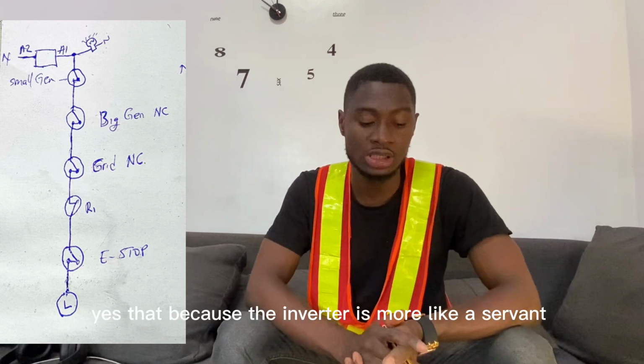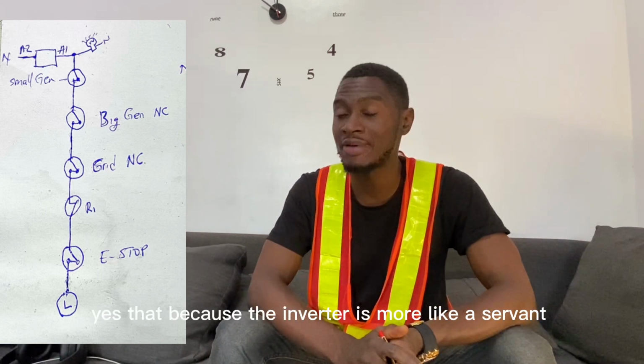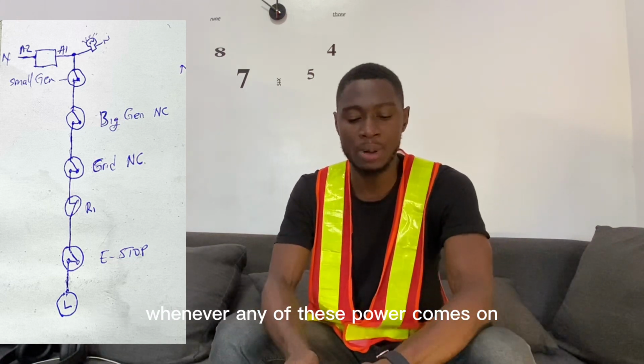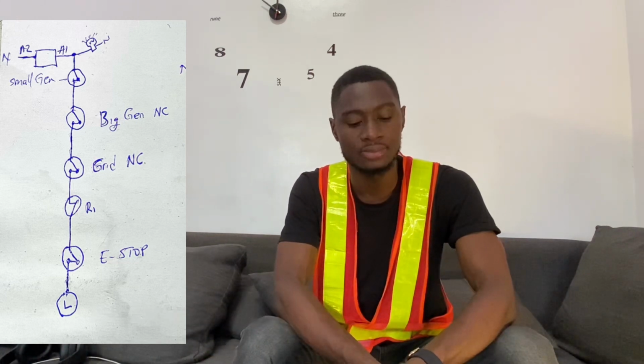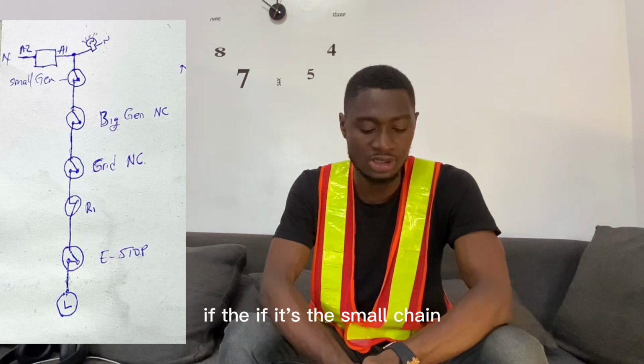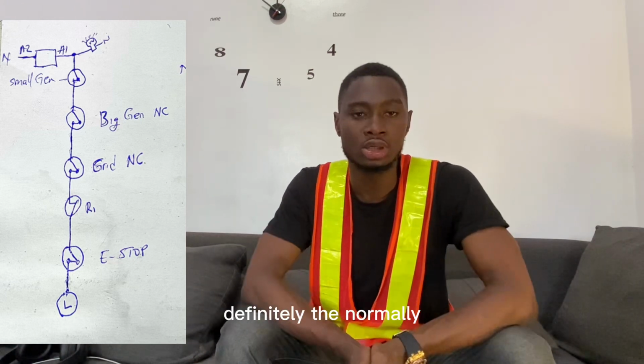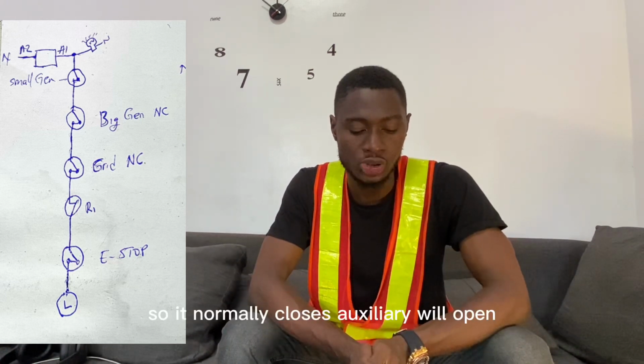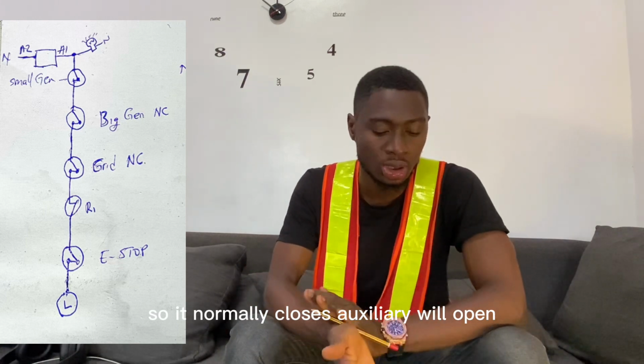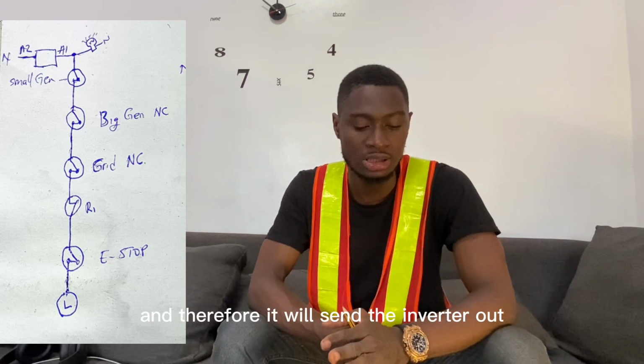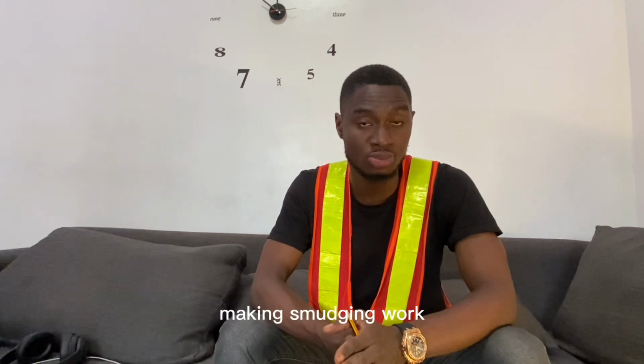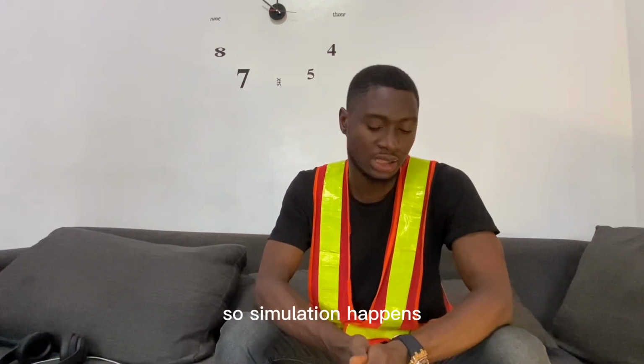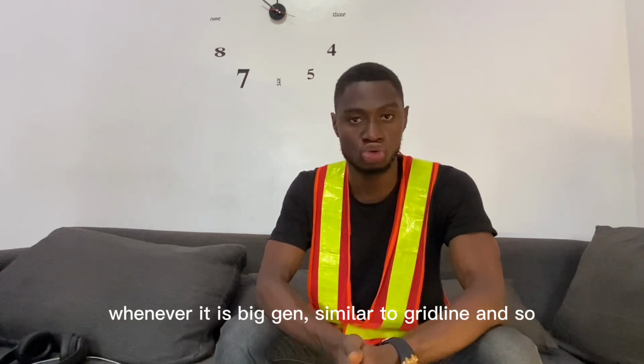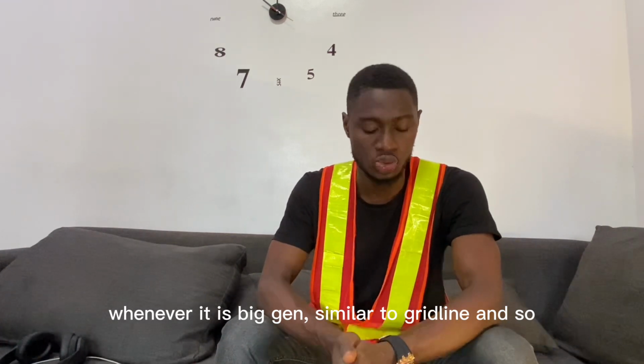That's because the inverter is more like the servant here. Whenever any of these powers comes on, it has to give way. If it's the small gen, the normally closed auxiliary will open, and therefore it will send the inverter out, making the small gen work. A similar thing happens whenever there's the big gen, the grid line, and so on.